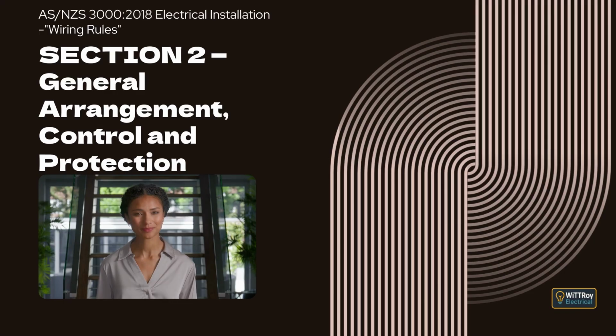Clause 2.5.7.2.3, General Supply Circuit Discrimination. For normal circuits, discrimination should be arranged so that if something goes wrong, the loss of supply is as small as possible. That means you coordinate the protective devices on the outgoing circuits with the protective device on the supply side. The coordination is checked using the time current curves for the devices, or using the manufacturer data.